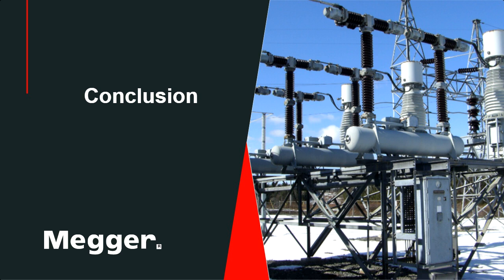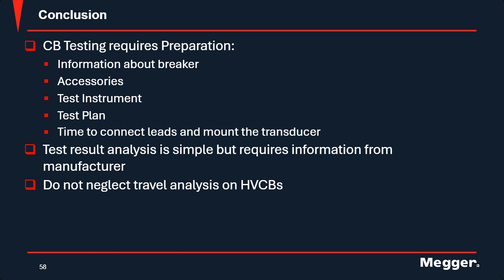And that pretty much wraps up what we wanted to talk about today. So we're just going to do a little bit of conclusion here. Circuit breaker testing does require preparation. So, information about your breaker: does it have pre or post resistors? Does it have capacitors? How many breaks per phase? Is it a live tank or dead tank? What kind of apparatus is it? Is it oil, SF6? What kind of transducer does it take? Can it use both? Does the manufacturer recommend one specific one? And obviously, the test result analysis is simple, but it requires information from the manufacturer.